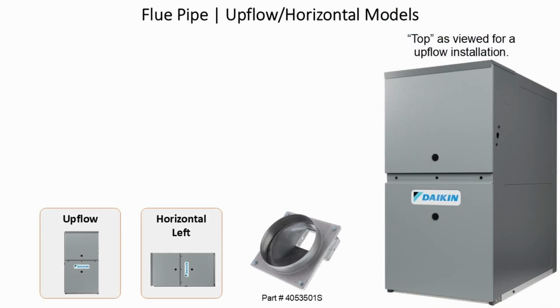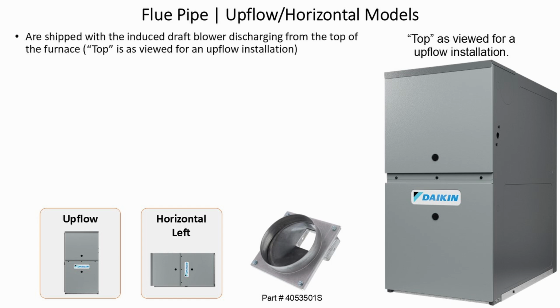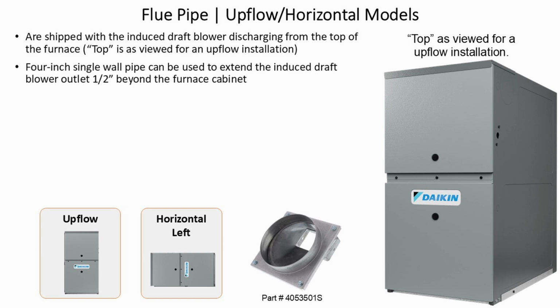Flue pipe upflow horizontal models. Upflow horizontal model furnaces are shipped with an induced draft blower discharging from the top of the furnace. Top is as viewed for an upflow installation. 4-inch single-wall pipe can be used to extend the induced draft blower outlet 1/2 inch beyond the furnace cabinet.